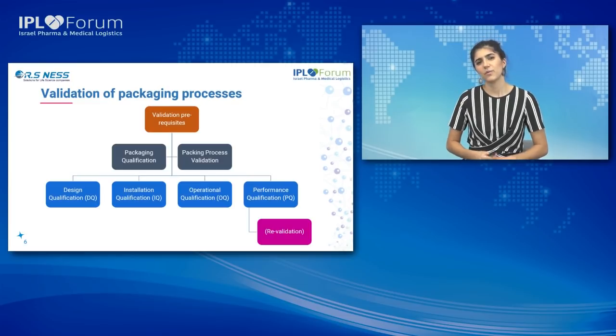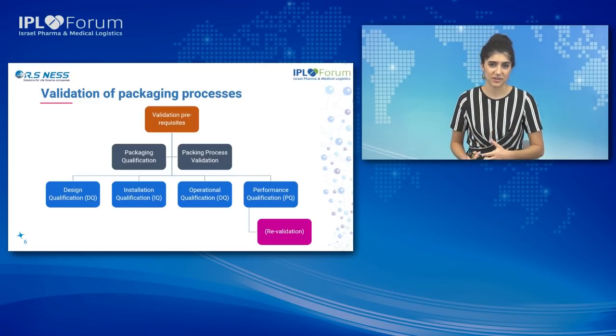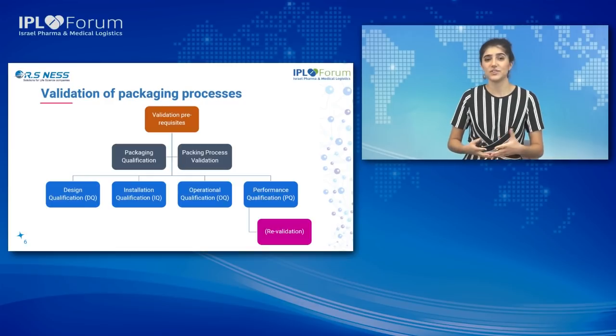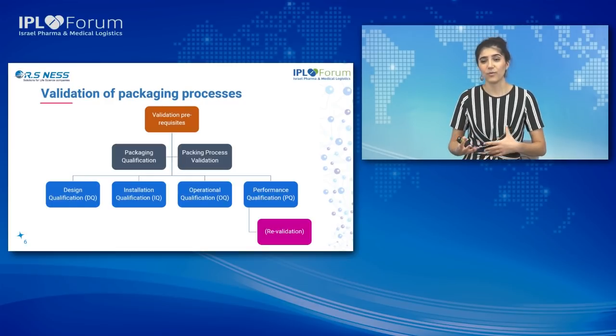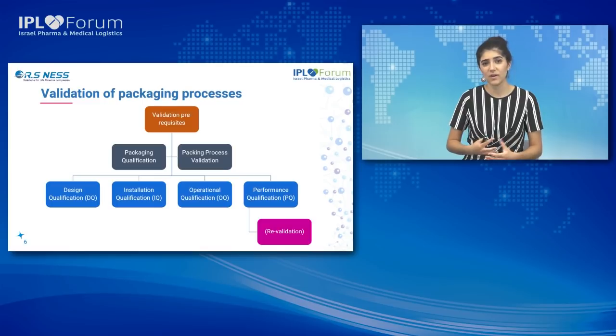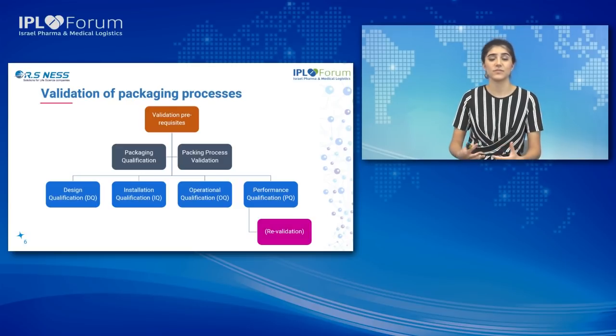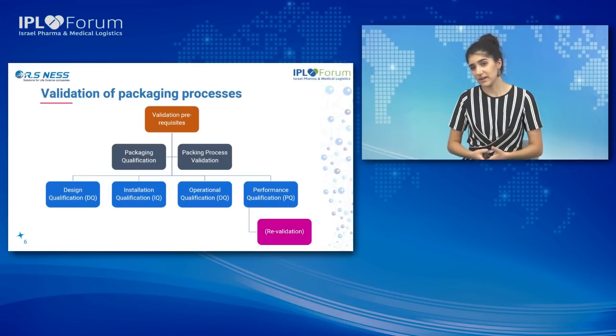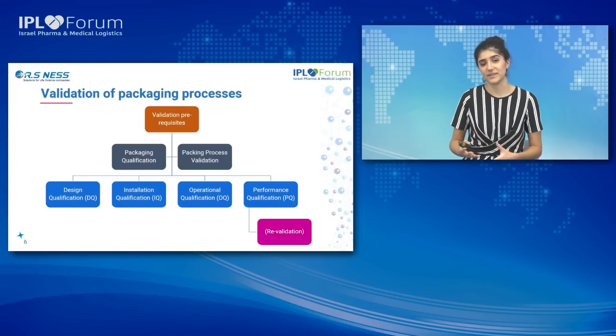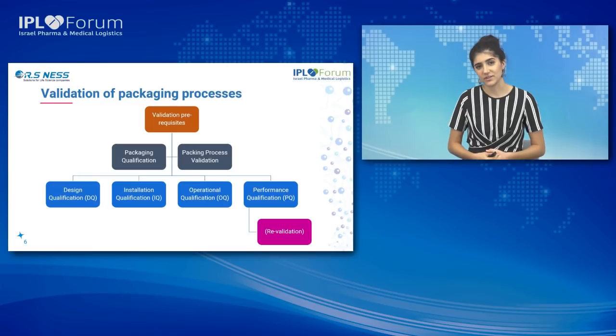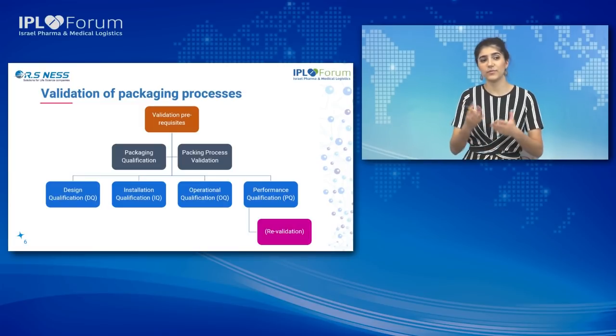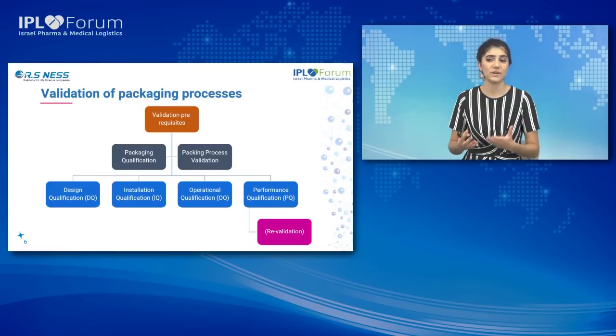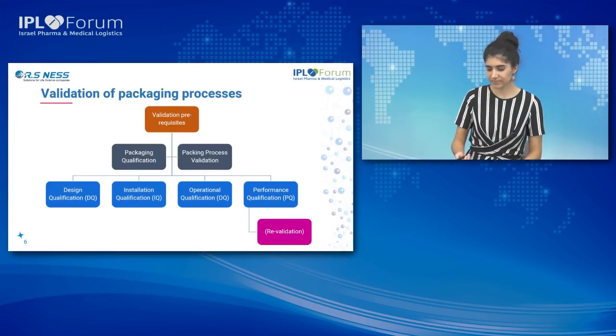Now, often we might have to do something called revalidation. That's generally done when there's been a change in your process, or there are new risks which have come into play, or customer complaints over something that you weren't aware of. If there's been a change in the materials, let's say, we might have to reconduct validation on our processes. What your company might also do, and that's depending on the company's procedures, we might redo validation every 1 or 2 years, or have a review board whereby you decide whether revalidation needs to be conducted.